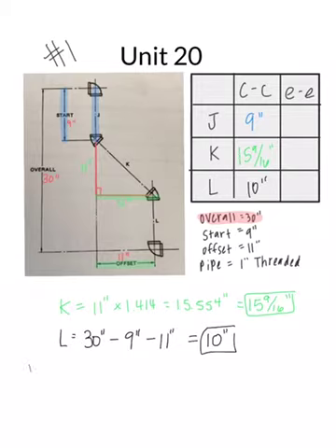And for pipe J, its center to center measurement is 9, and I'm going to be taking off. So I'm going to 1 inch threaded, and J is between a 90-degree fitting and a 45-degree fitting. Here's our 90 and here's our 45. So the takeoff for a 90 is 1.5, so take off 1.5. And the takeoff for a 45 is 1 1/8. And then my threads I have to add back on, a 1/2 inch per fitting.